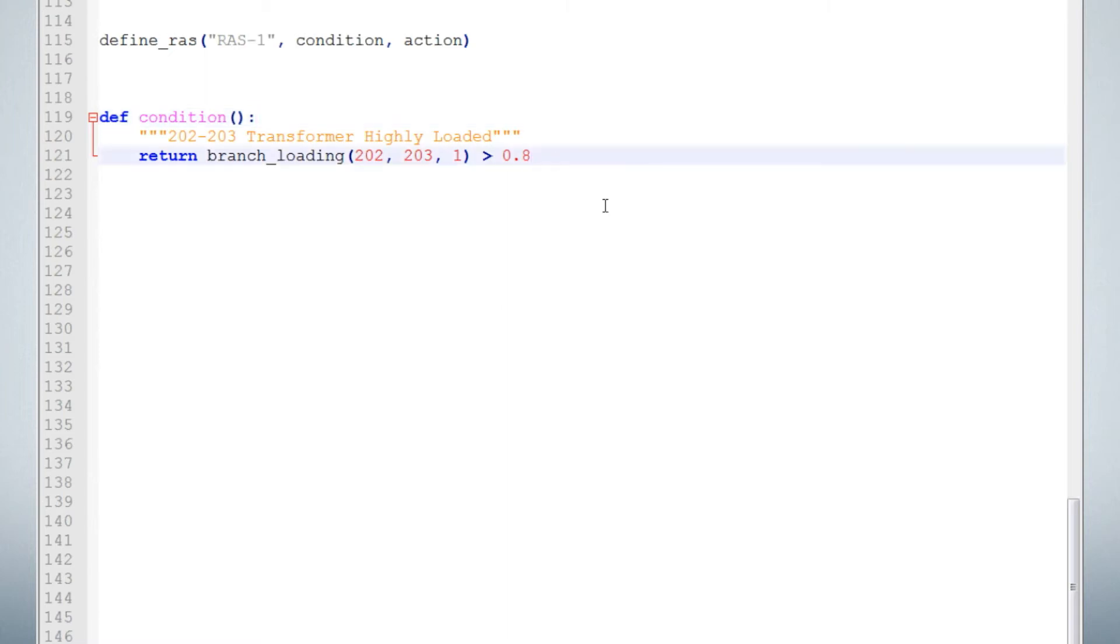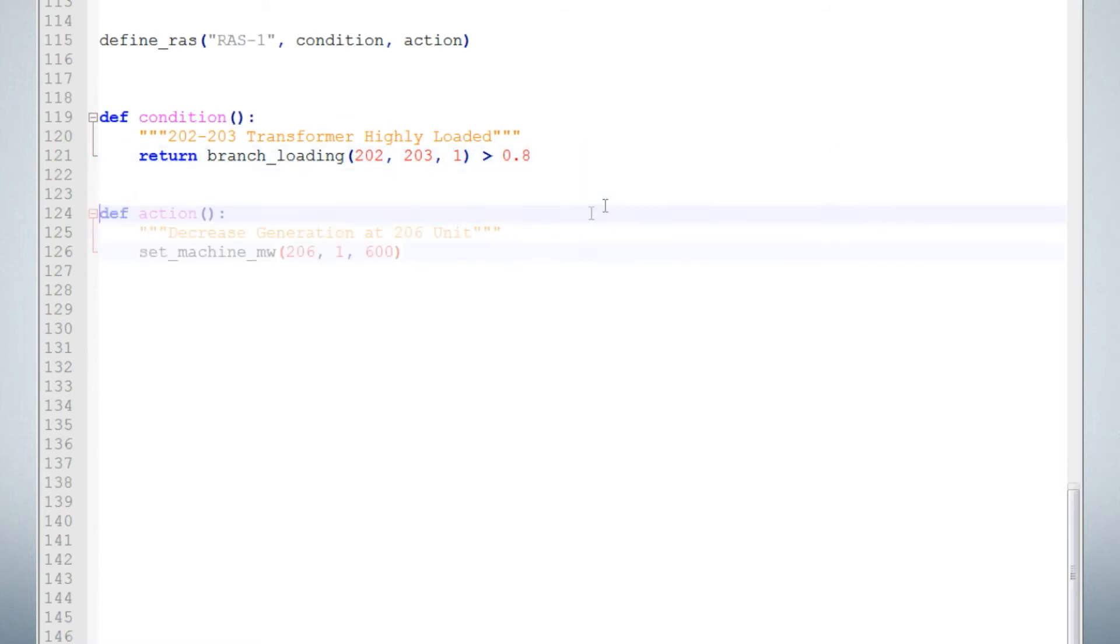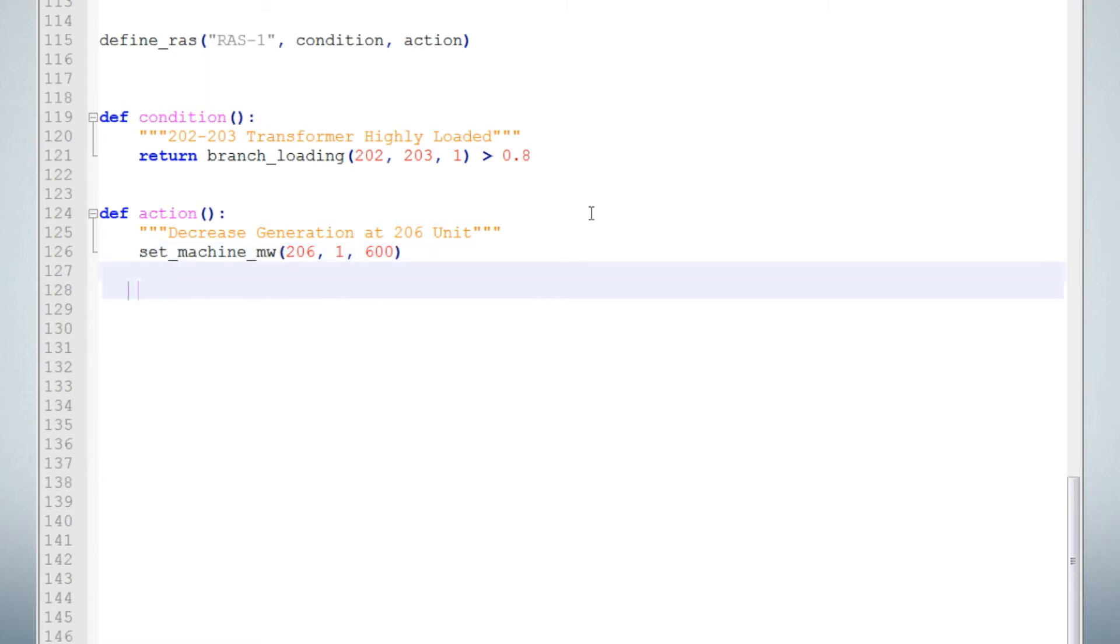Next, type this action function. This function will set the megawatt output of the unit at bus 206 to 600 megawatts. Now type the define RAS statement to tie the functions together. Save this RAS.py file.